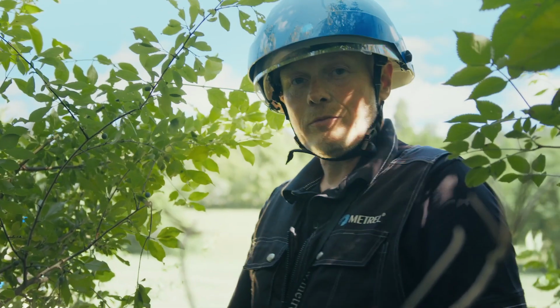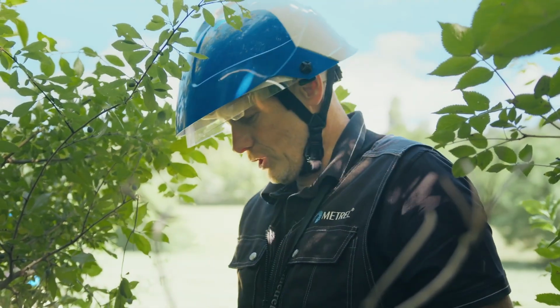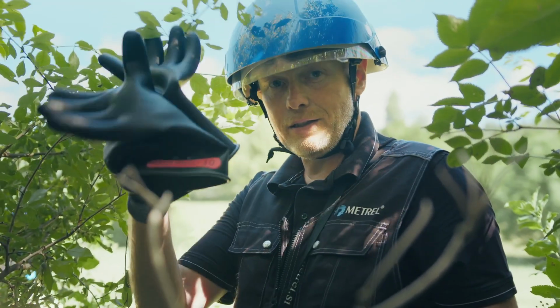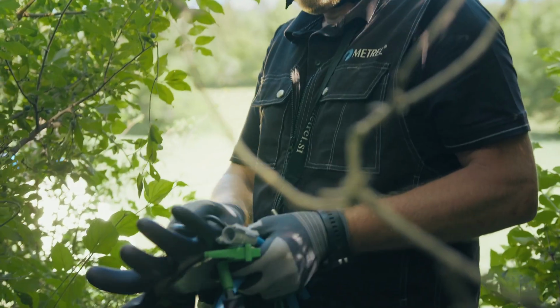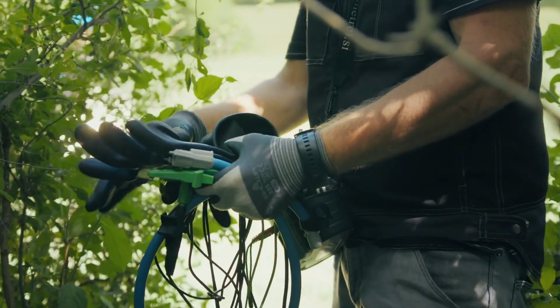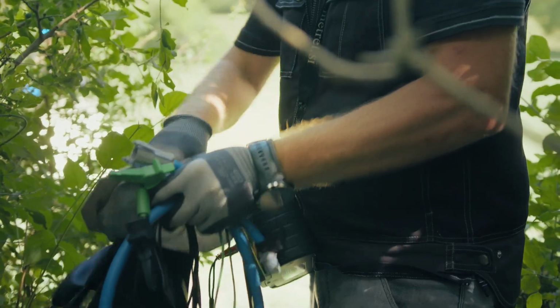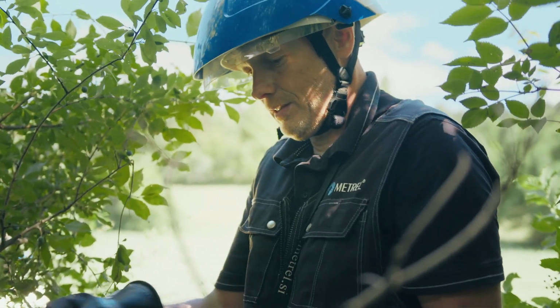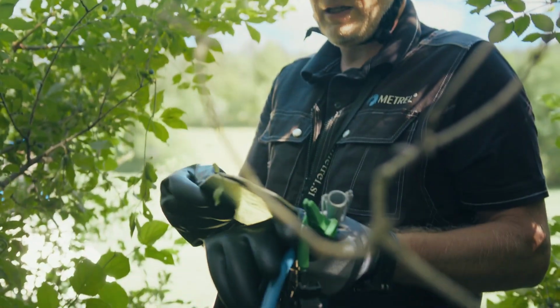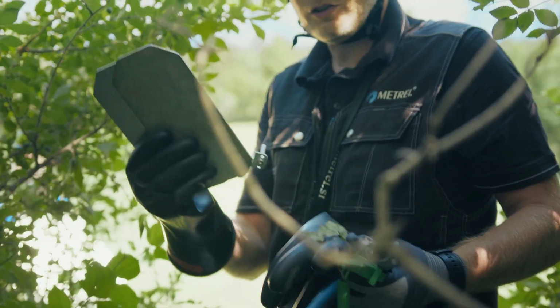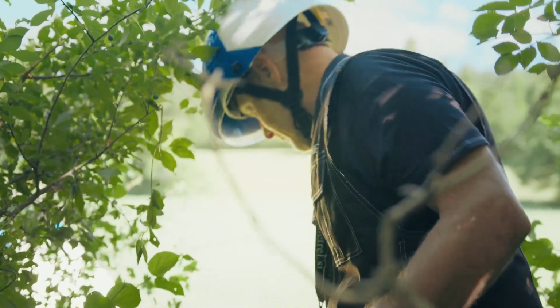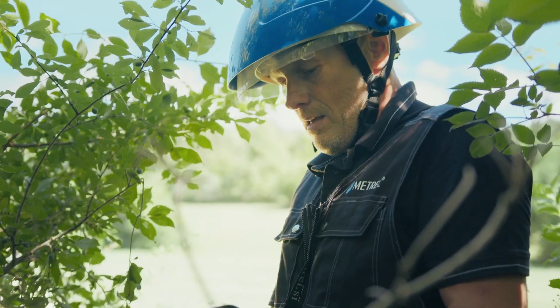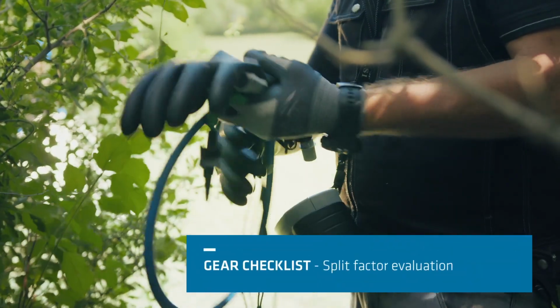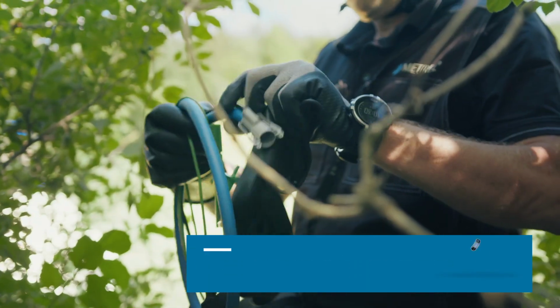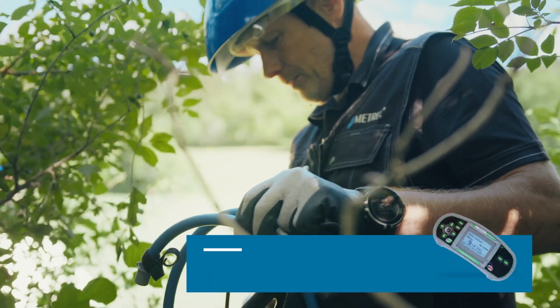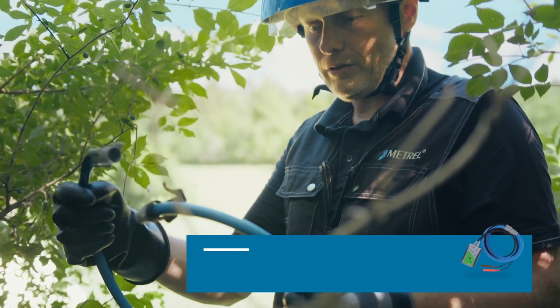Now in the second stage of the measurements, we will use the step and touch method. We still need the electric gloves because you never know what can go wrong. We will use the touch plates, which are 200 square centimeters, and we will step on them to simulate 50 kilos for the body simulation. Additionally, we will measure the split factor of this pylon. For this purpose, we have flexible clamps to connect around each leg.